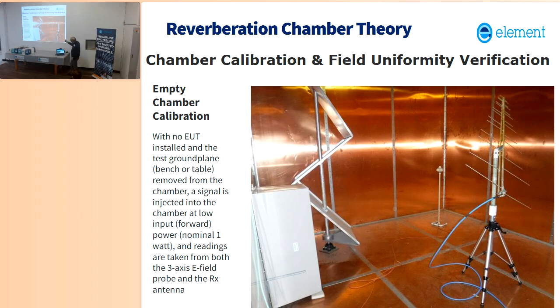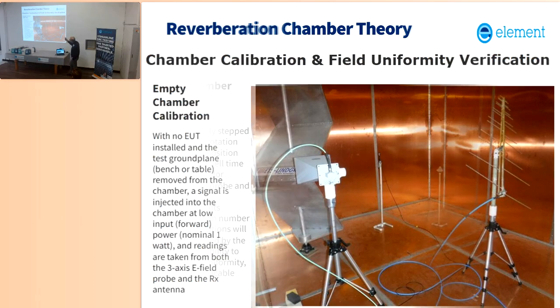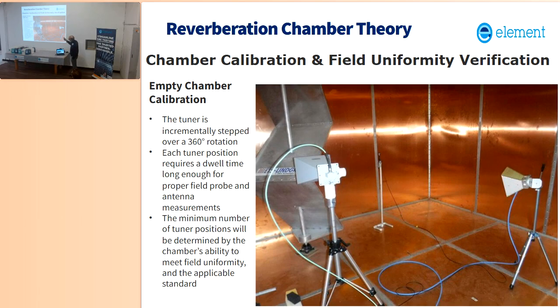And you step through. Normally you use 1 watt of power, makes the math easy. And then you just move that probe around and move that antenna around through all the different positions. And in DO-160, the currently available standard, DO-160H is different, of course, like I said, but in all the standards out there, you move the tuner incrementally over a 360-degree rotation. You stop at each position long enough to make the measurements with the probe and the antennas.